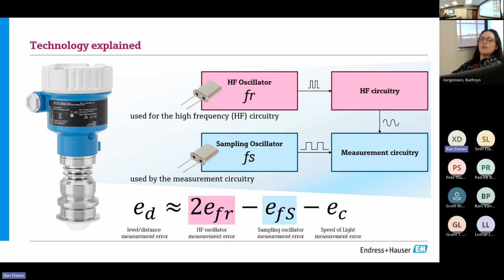The idea is if I've got two different high frequency systems, one's performing the measurement, one's purely a control. If I notice either one start to drift at all, I can trigger an advance warning that my level or measured distance is going to quickly go out of tolerance. Even though there's only a 50% chance it's the specific circuitry we really care about, this allows us to have some type of traceability inside a device that frankly is challenging, if not impossible, to actually calibrate.